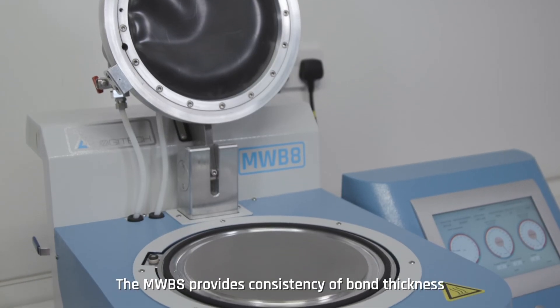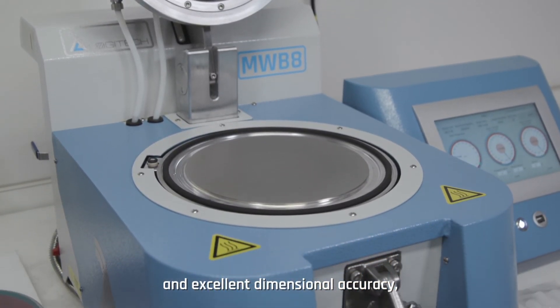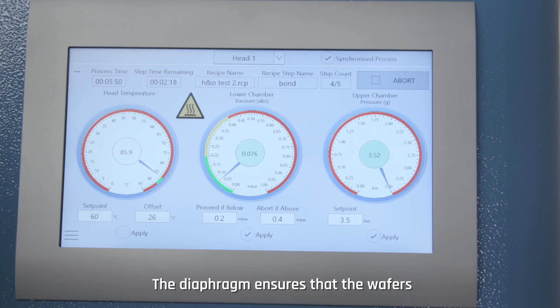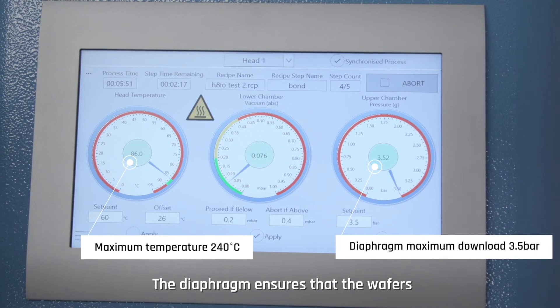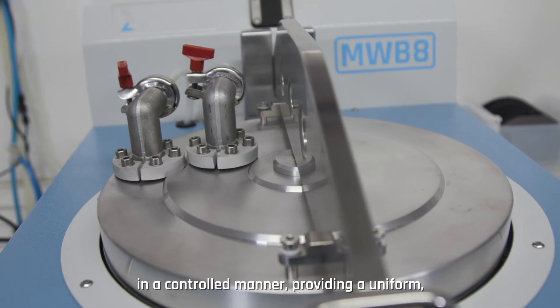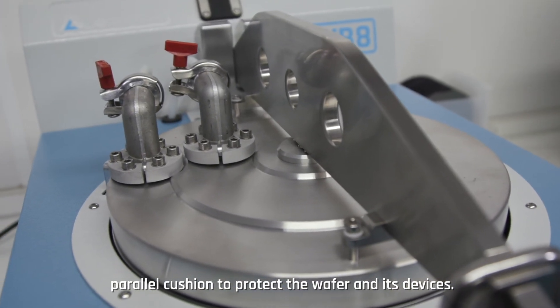The MWB8 provides consistency of bond thickness and excellent dimensional accuracy due to the precise control of a flexible diaphragm within the bonding chambers. The diaphragm ensures that the wafers are pressed into the melted wax or resin layer in a controlled manner, providing a uniform parallel cushion to protect the wafer and its devices.